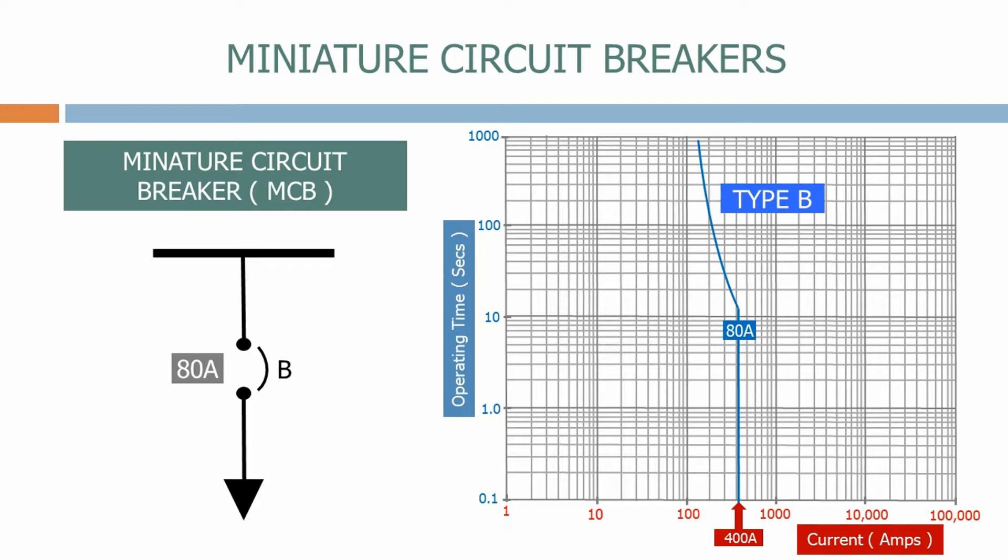MCBs come in all different ratings and as you would expect as the rating decreases we move to the left of the current axis and the MCB will trip instantaneously at a lower current magnitude.